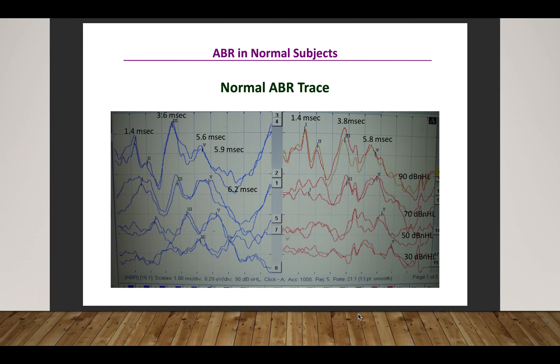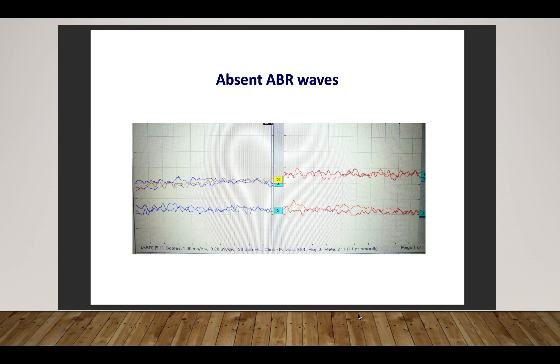This is a normal ABR. We can see identifiable, repeatable ABR waves down to 30 dB nHL, reflecting normal hearing in the frequency range 2 to 4 kHz. This is an example of absent ABR waves — no identifiable nor repeatable ABR could be traced at maximal stimulation of 90 dB nHL.